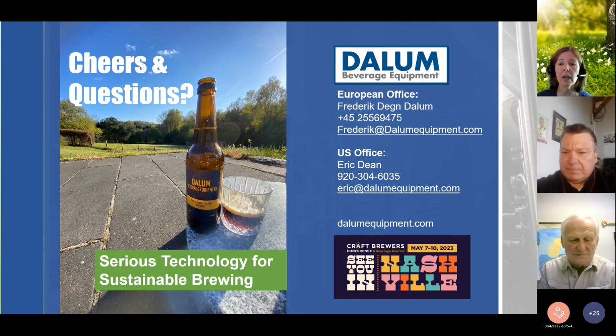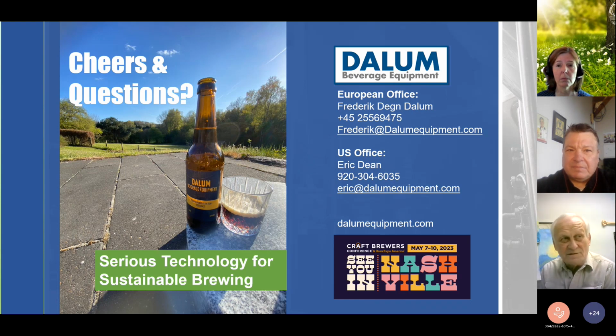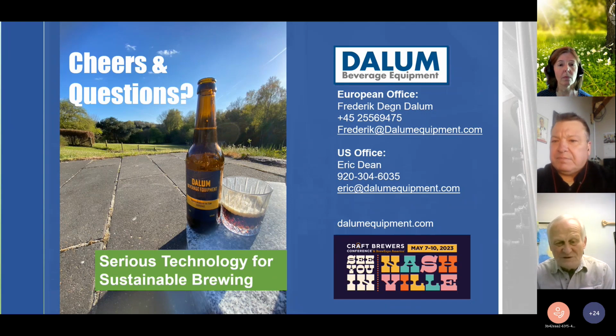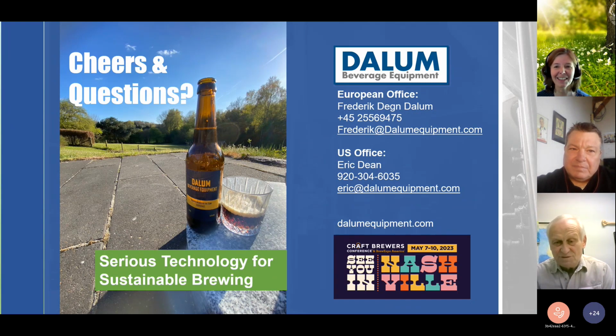We have another question. What are the glycol system horsepower and BTU requirements for the larger units? The biggest unit we make right now is the 30 pound per hour. The motor on that is 2.2 kilowatts or 3 horsepower. And the refrigeration load is about 7,000 BTUs per hour. If you go to a Home Depot or somewhere and try to buy a small window air conditioner, the smallest one you're going to find is about 9,000 BTUs per hour. So as a reference, we're basically window air conditioner size on the refrigeration.